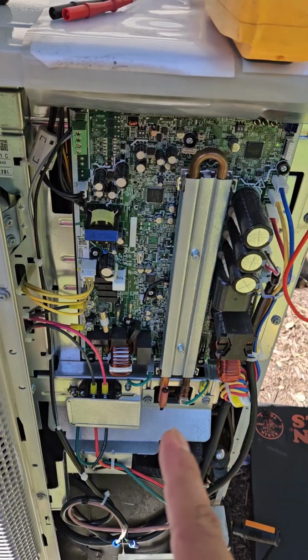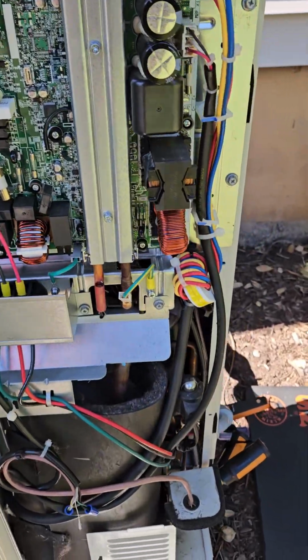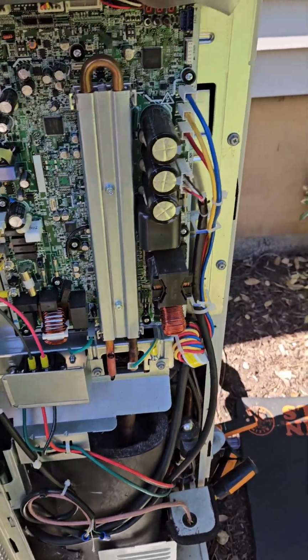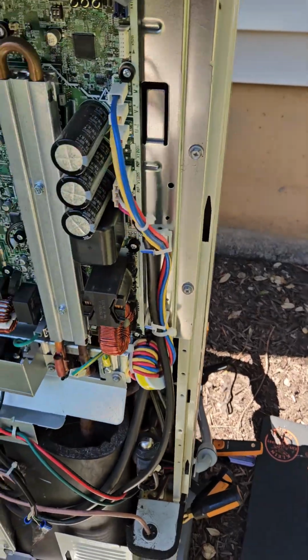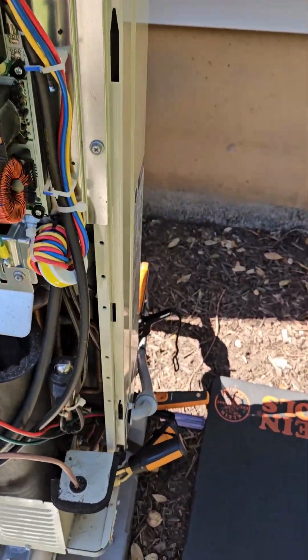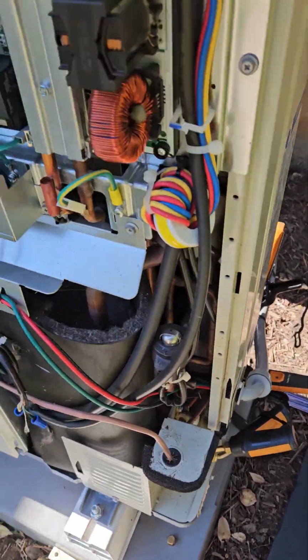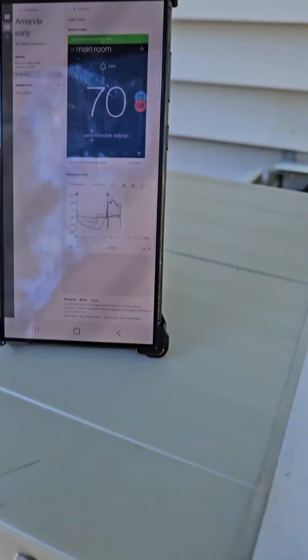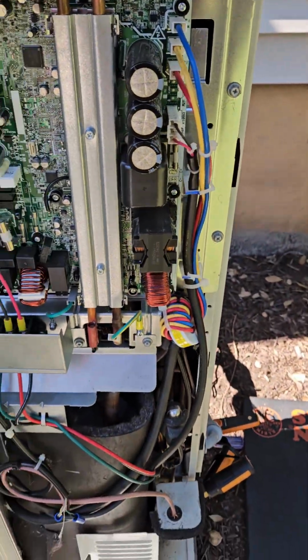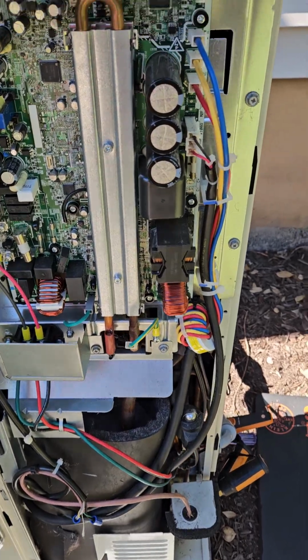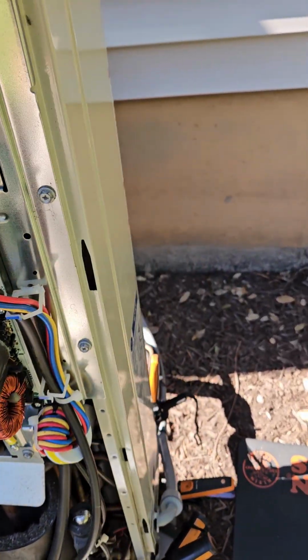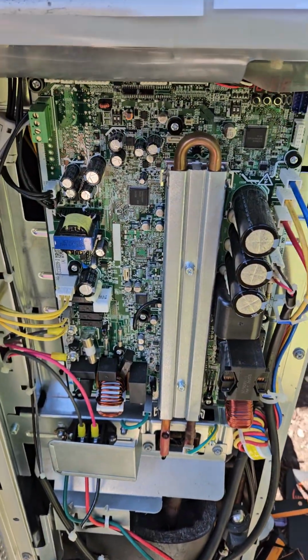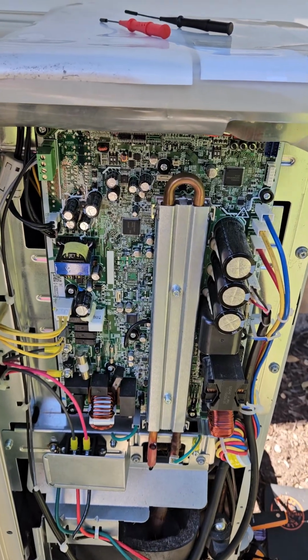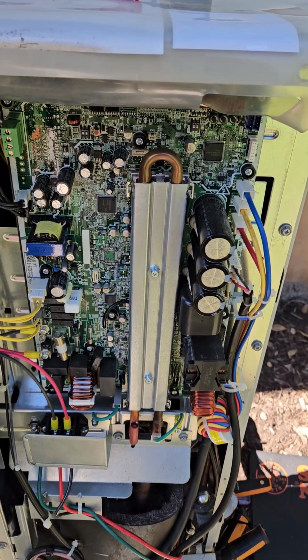Stay tuned. Okay, so after running the unit for about 10 minutes in test mode, everything came on just fine. There's nothing wrong with the pressure, superheat and subcooling are okay, and we already set it back to the regular settings. So yeah, there's nothing wrong with it. So I guess it was a glitch in the software, but if it happens again, I guess we will start with the pressure sensor and go from there.